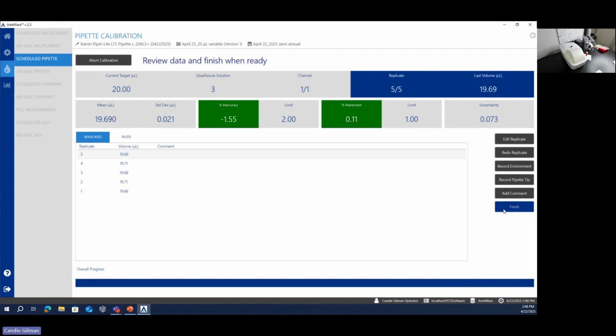All right, so now I've reached the end of that 20 microliter data set. If I take a look at my tolerances, I'm within that plus or minus 2%. This pipette's under delivering a little bit, but it's within tolerance, so I'm happy. And then imprecision is also well within tolerance. So there aren't any data points that I want to redo, but what I would like to do is add a comment. So maybe I change the seal and the O-ring on this pipette. So I'll go ahead and make that comment.